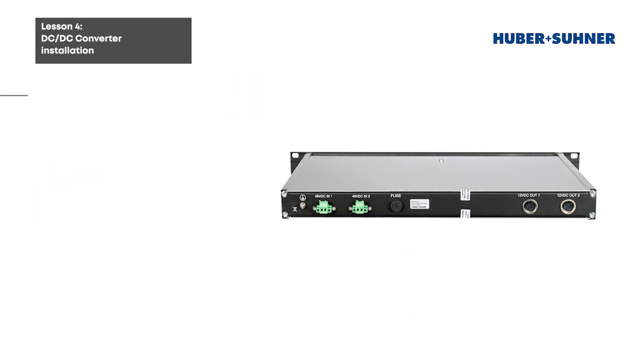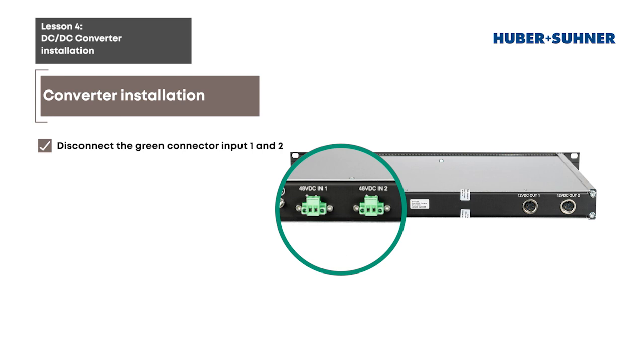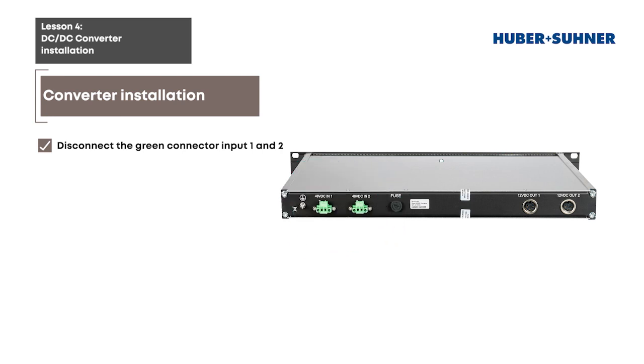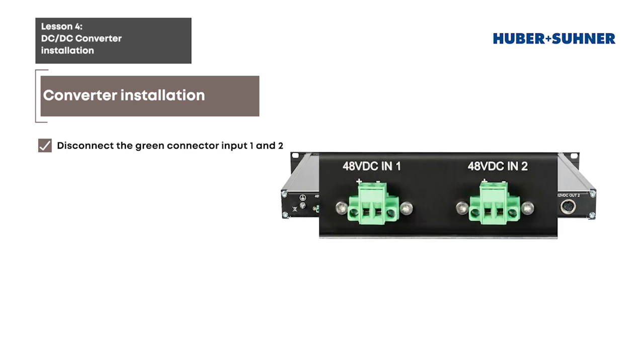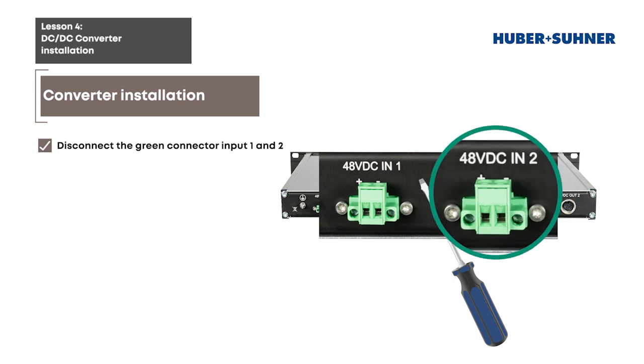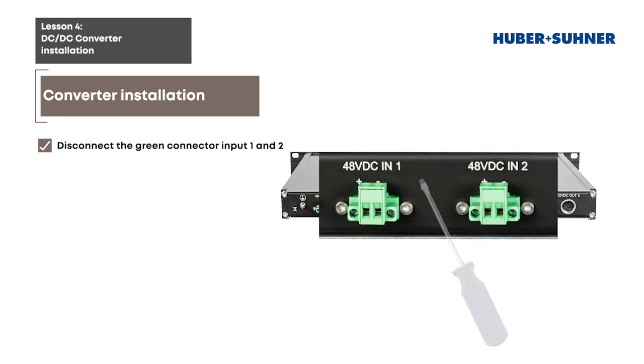Disconnect the green connector from 48-volt DC input 1 and 48-volt DC input 2. Connectors are secured by screws, so tools will be necessary. The unit is designed for dual power supply usage for redundancy reasons. If only one single power line is available, the 48-volt DC input 2 connector can stay unconnected.